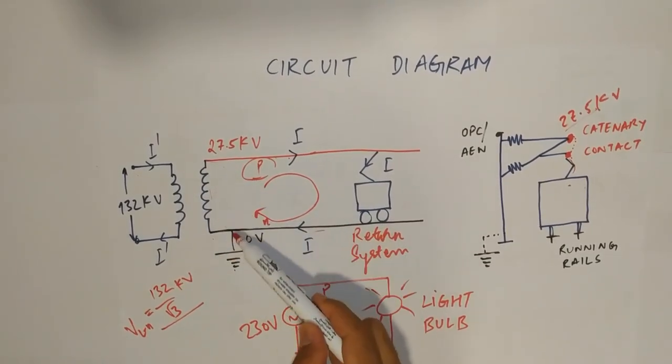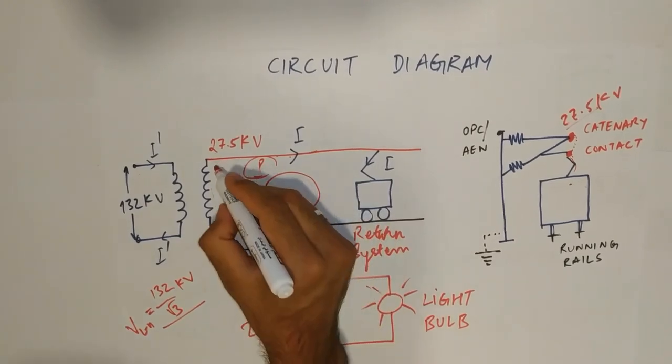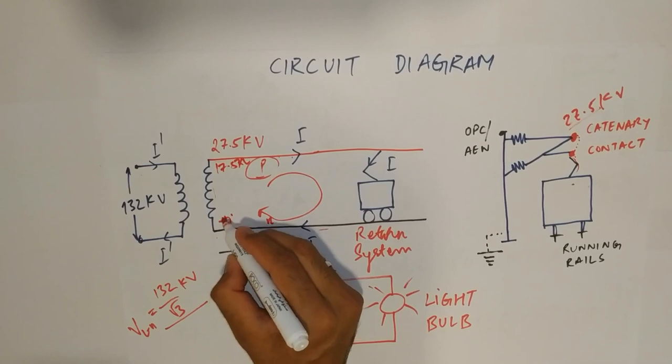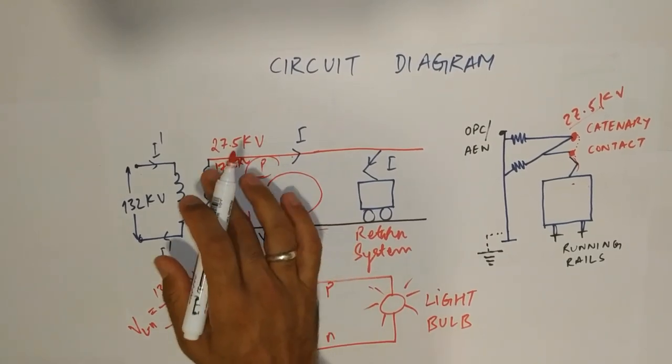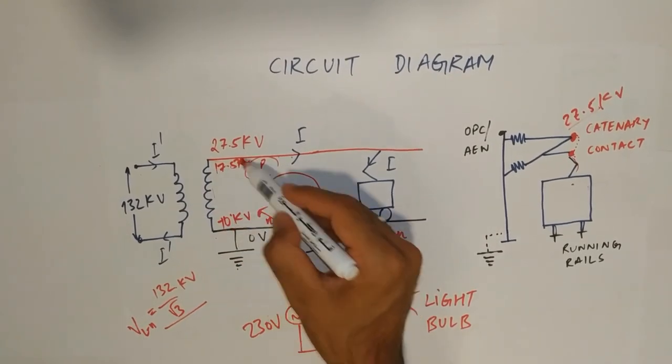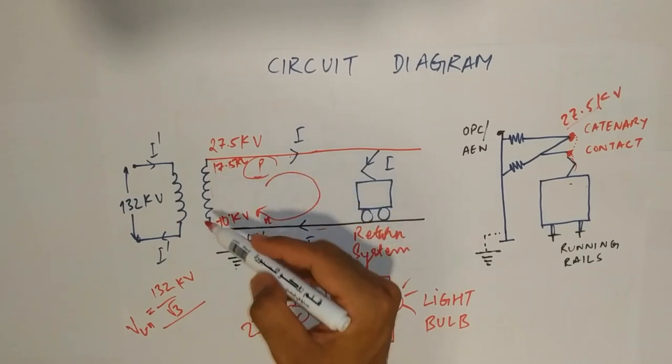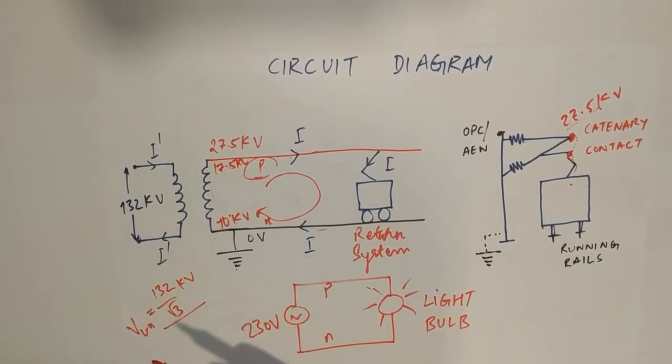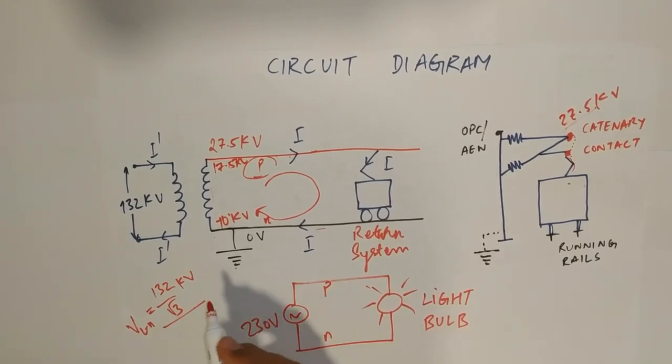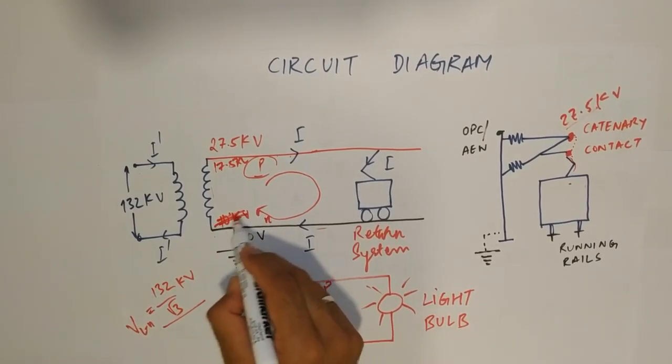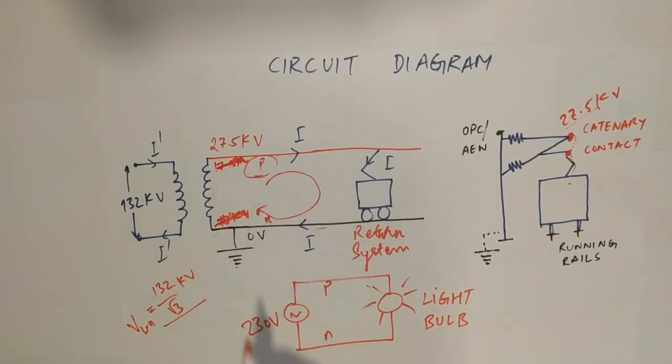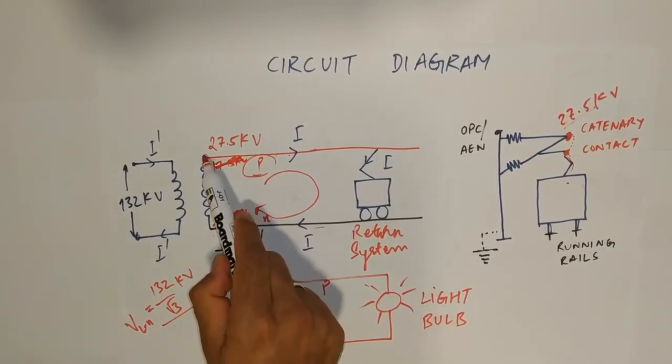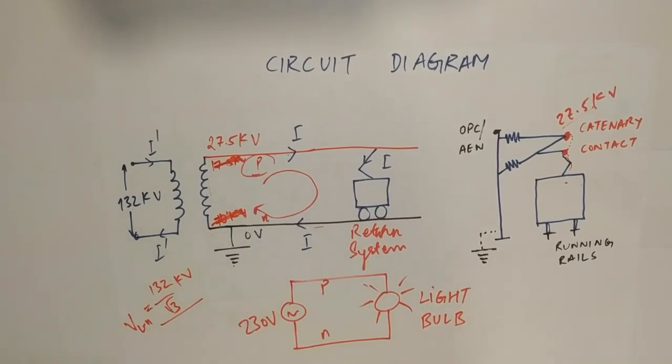Now, this voltage can be either 17.5 here and minus 10 KV. So, you will be getting 27.5 as the difference between these two points or it can be 15 and this can be minus 12.5 KV. But, to avoid this, what we do, we earth this point. Once you connect this point to earth, then you will get 27.5 KV at this point.